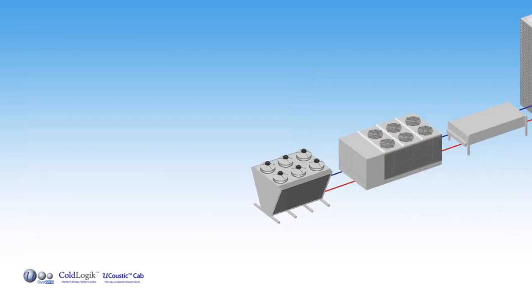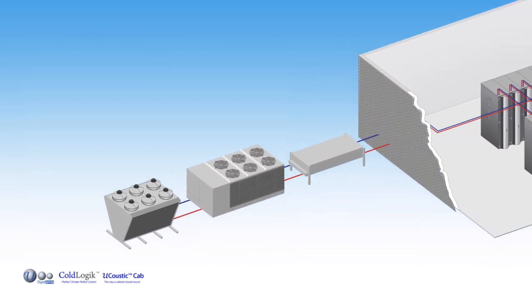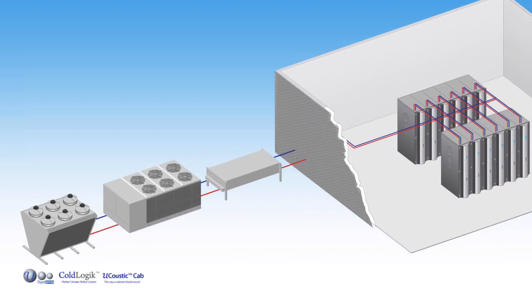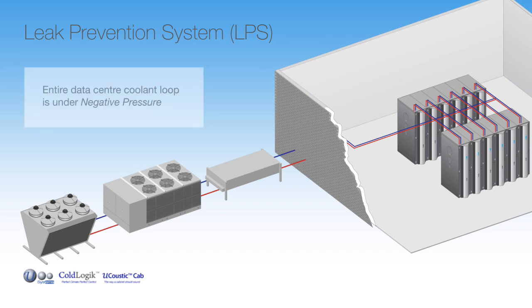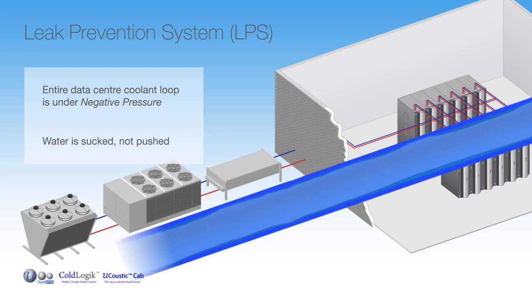For safety and peace of mind, ColdLogik is the only water-cooled solution in the world which has the option of a leak prevention system. This is not to be confused with leak detection systems, which are commonly used in current competitor water-cooled solutions and older CRAC systems. The LPS puts the whole data center coolant loop on a negative pressure circuit, with the water being sucked rather than pushed around the system, ensuring that leaks cannot occur.